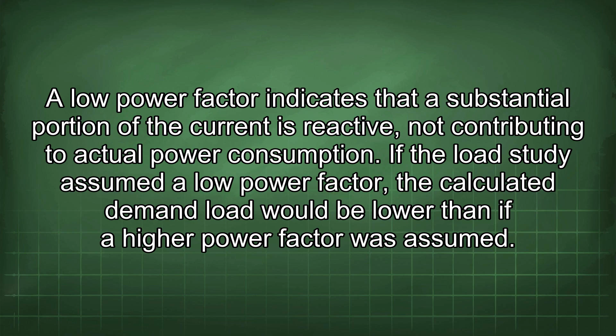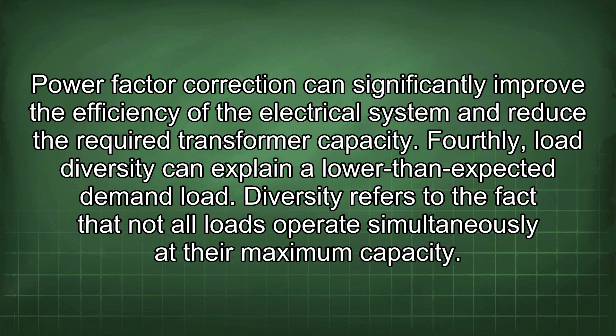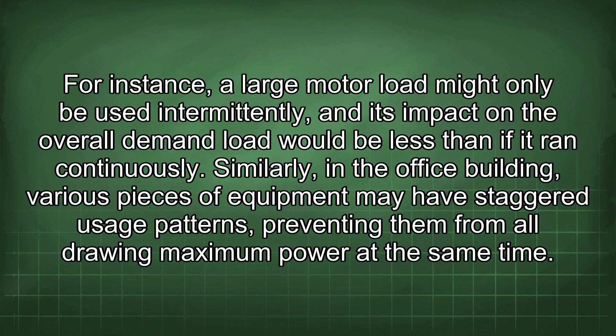transformer capacity. Fourthly, load diversity can explain a lower than expected demand load. Diversity refers to the fact that not all loads operate simultaneously at their maximum capacity. For instance, a large motor load might only be used intermittently, and its impact on the overall demand load would be less than if it ran continuously. Similarly, in the office building, various pieces of equipment may have staggered usage patterns, preventing them from all drawing maximum power at the same time.